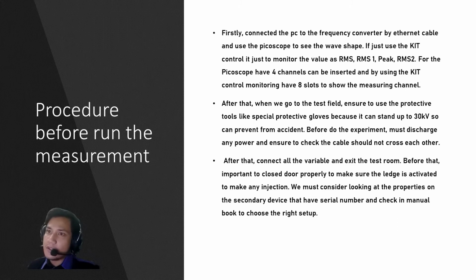If we just use the kit control, it is just to monitor the values as RMS, RMS1, peak and RMS2. For the picoscope, 4 channels can be inserted, and by using the kit control monitoring, there are 8 slots to show the measuring channels. For the second point, when we go to the test field, ensure to use protective tools like special protective gloves because they can withstand up to 30 kilovolt, so they can prevent any accidents. Before doing the experiment, we must discharge any power and ensure the cables do not cross each other.